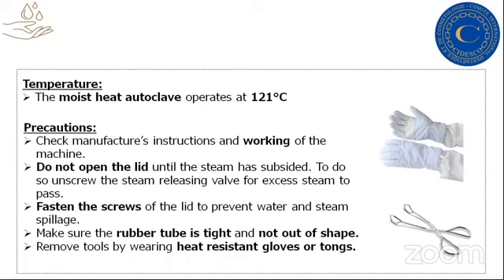Now, the moist heat autoclave operates at 120 degrees Celsius, which is ideal for metal instruments. But I would always urge and request you to read the manufacturer's instructions well, because there are many kinds of autoclaves in the market. You need to learn the screwing and unscrewing of all the attachments, and understand how the meter gauge works. Otherwise, if you don't fit the lid well, you might face a problem, like the lid coming out, or the instruments not getting cleaned so well.